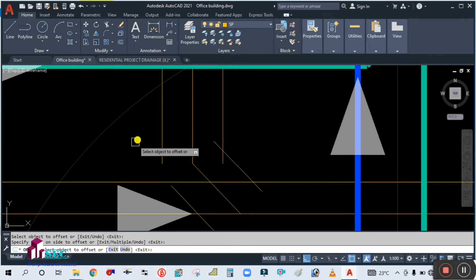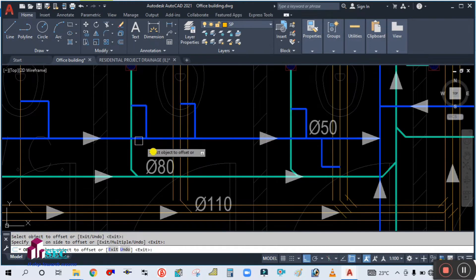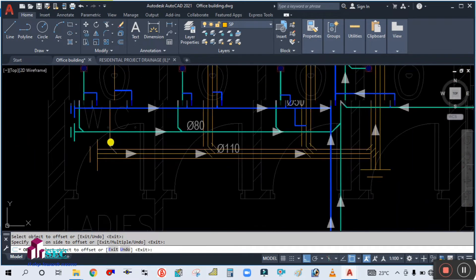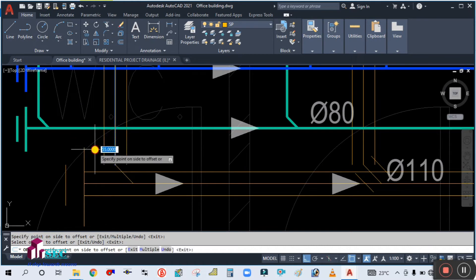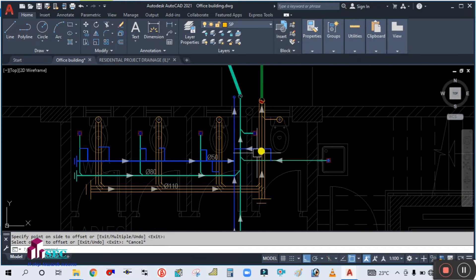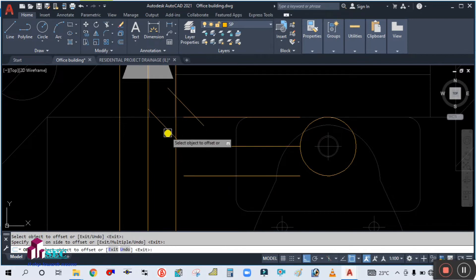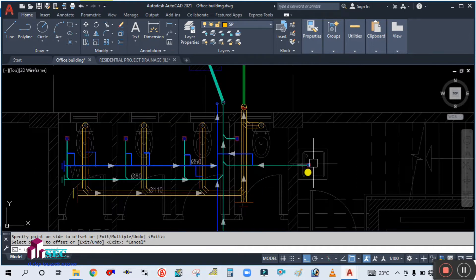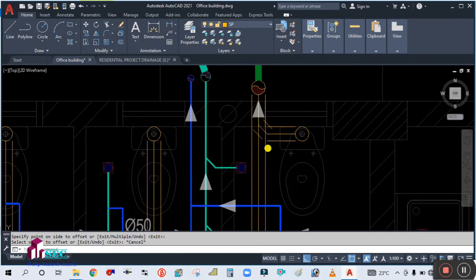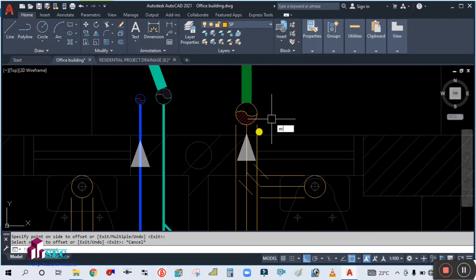Simply select and offset each line. This is drafting — it is not required for the design engineer, but as a draftsman this is very important. After single line drawing, you need to create the double line drawing, also called a shop drawing. You can see it is already converted into the double line. Now we are going to place the fittings — you can see a branch coming here, so just extend it.